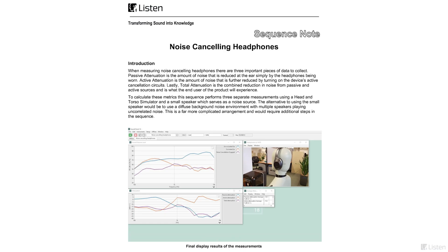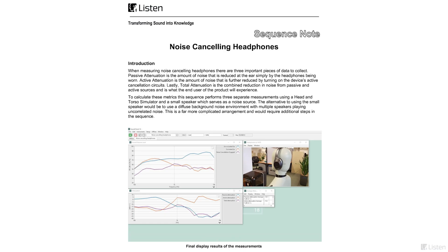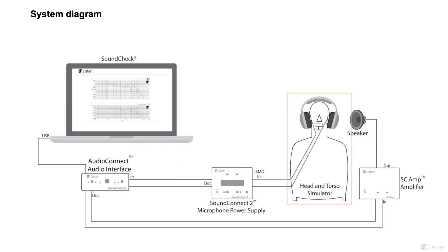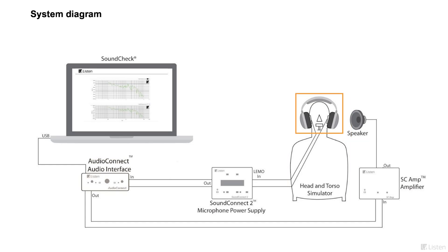We even have a pre-written sequence showing off this functionality called 'noise cancelling headphones,' available on our website. You will need a head and torso simulator, or an acoustic ear simulator with an artificial pinna, at least one speaker for background noise generation, and a set of headphones with ANC.